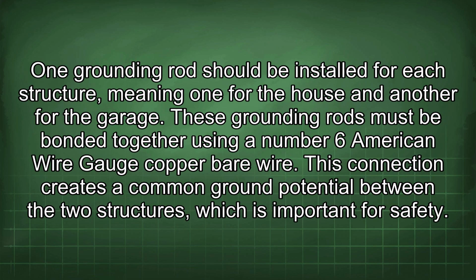One grounding rod should be installed for each structure, meaning one for the house and another for the garage. These grounding rods must be bonded together using a number 6 American wire gauge bare copper wire. This connection creates a common ground potential between the two structures, which is important for safety.